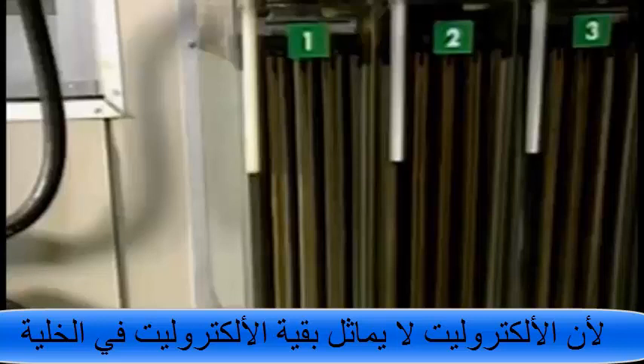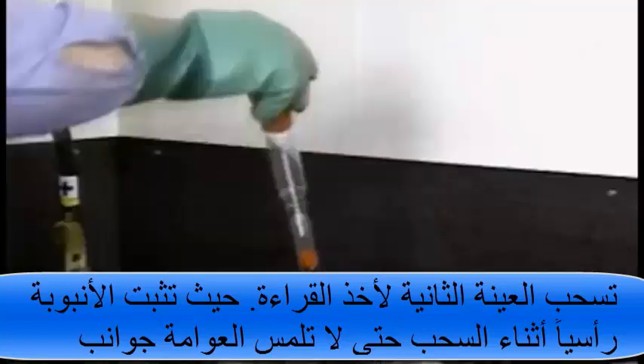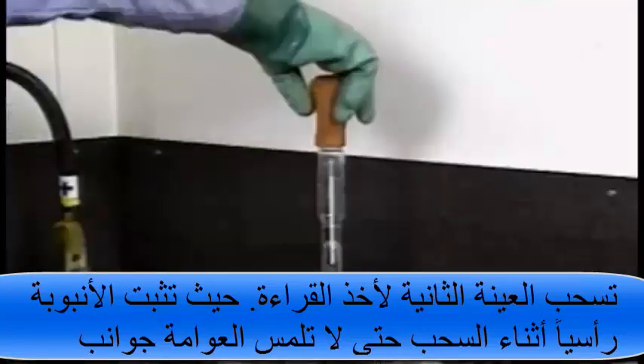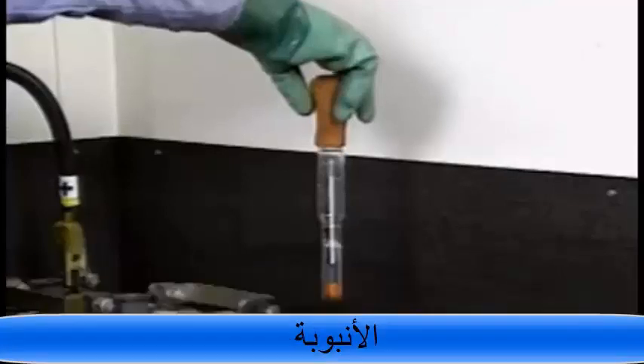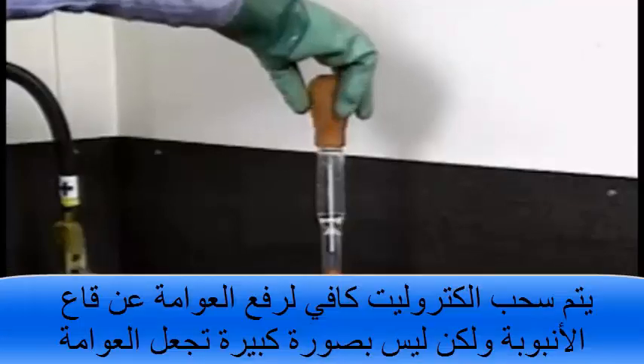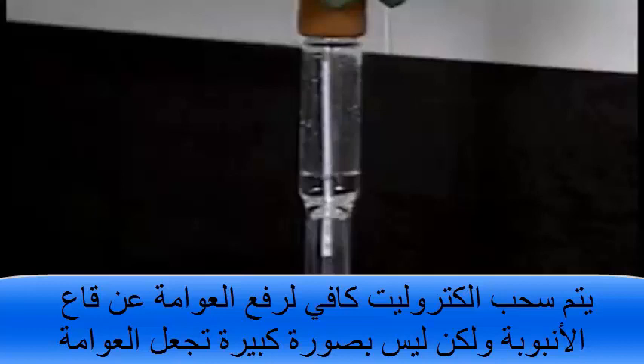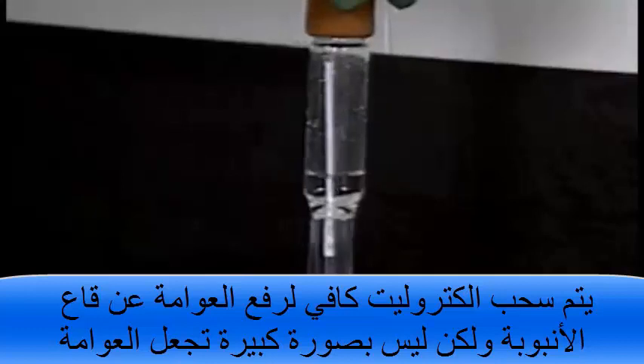of the rest of the electrolyte in the cell. A second sample is drawn for the specific gravity reading. While a sample is being drawn, the syringe is held vertically so the float doesn't touch the sides of the barrel. Enough electrolyte is drawn to lift the float off the bottom of the barrel, but not so much that the float hits the top of the barrel.